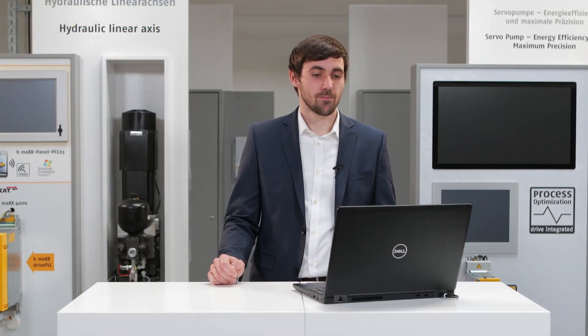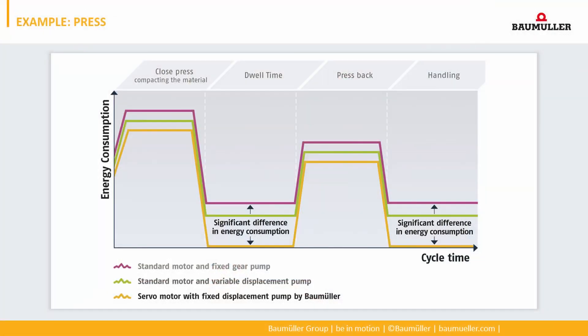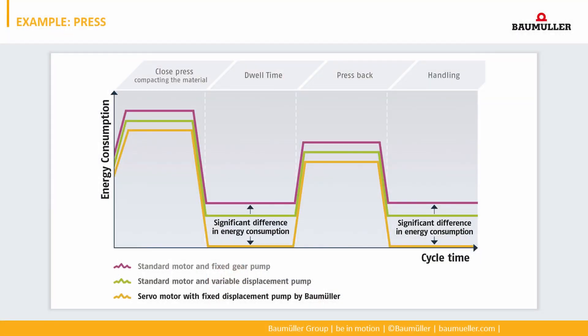Now I'd like to show the energy consumption of three different solutions using two application examples. The first is a press. In this diagram, the purple curve shows a standard motor with fixed gear pump, the green curve shows a standard motor with variable displacement pump, and the yellow curve shows a servo-hydraulic system. During dwell time and handling, the energy consumption is much smaller in a servo-hydraulic system because no flow rate is necessary and the motor is at standstill. At hydraulic systems with standard induction motor and variable displacement pump, the motor still rotates at nominal speed but there is no flow rate, resulting in much higher energy consumption. At a system with standard motor and internal gear pump, the energy consumption is still higher because of the constant flow rate.